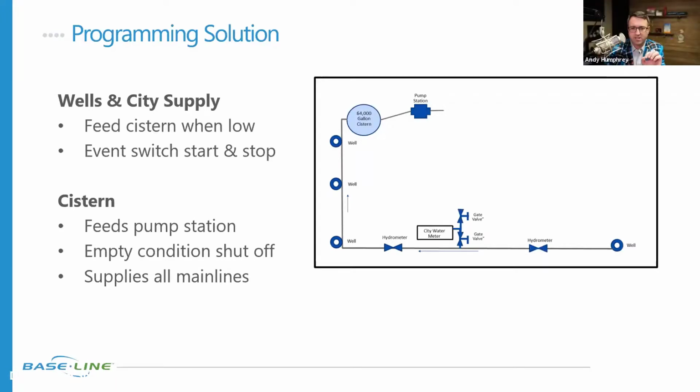So Idral, are they using our event decoder, or are they using our pressure decoder? No, good question. I knew that was coming. So it's coming into their system, and it's going into one of their devices, and it's providing us a signal after the fact, either an open or a closed situation. We can do the same thing now with our pressure transducer decoder, and hopefully in future designs we'll be doing that. But in this instance, we're taking just a simple open or closed signal from the pump station to do what we need to do.